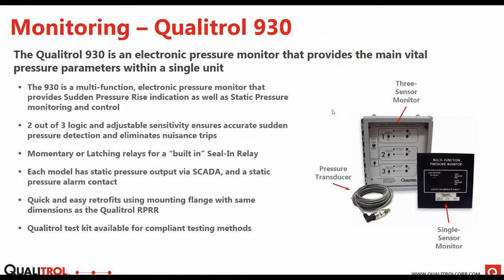Another upgrade that you could consider with monitoring is our Qualitrol 930. This would replace the traditional rapid pressure rise relay or sudden pressure relay with a more advanced solution. For example, one of the big features is 2 out of 3 logic for sudden pressure indication, and also adjustable sensitivity. What the 2 out of 3 logic does is that it makes sure that it needs to sense 2 or more sudden pressure occurrences in the tank to actually trip or alarm. This is done using 3 pressure transducers on the tank. They can be in 1 location or 3 locations, and they have adjustable sensitivity to ensure accurate sudden pressure trips and eliminate nuisance trips. So if you have an older unit with very high vibration or in a seismic zone, this would be a great option for that.